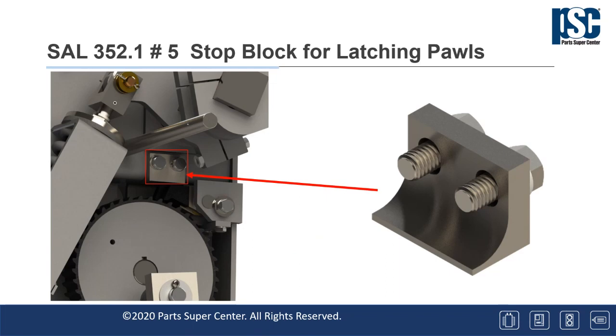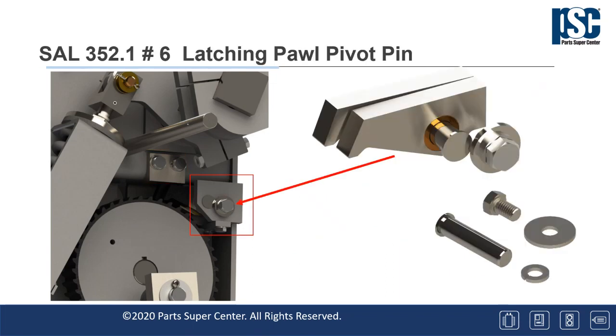Last but not least is number 6 on SAL 352.1, which replaced the latching pawl pivot pin with a redesigned captive hinge pin for increased reliability and ease of maintenance. Although they passed the original design life testing, once again, operational experience indicated the original design was not as reliable as desired. This change was introduced into production on breakers manufactured in 1979 and later. This advisory is recommended to be added if the latching pawls are being replaced. Ordering information, again, will be included in the service advisory accompanying these slides.